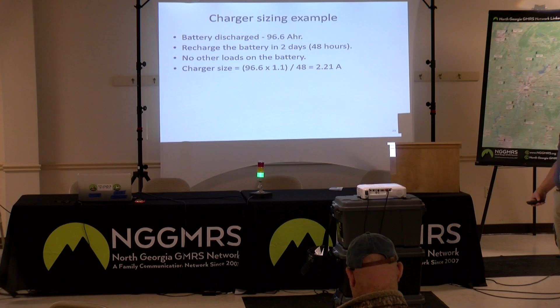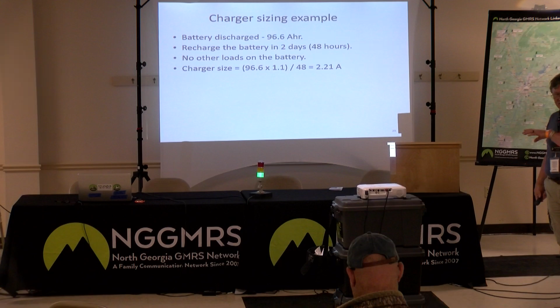So not actually 25, because we said the standby current was 2.3 amps. So I've got 22.7 amps available that the transmitter doesn't need, that I can now put into the battery. So a 25 amp charger would do the job with the duty cycle I'm using. You don't have to, and I mentioned the 96.6 times 1.1 - well, if I used 1.0, that would drop to basically just a touch over 2 amps. That 0.2 of an amp is not a big deal at the level we're working. But if you want to get precise with a different battery, just use a different recharge efficiency.